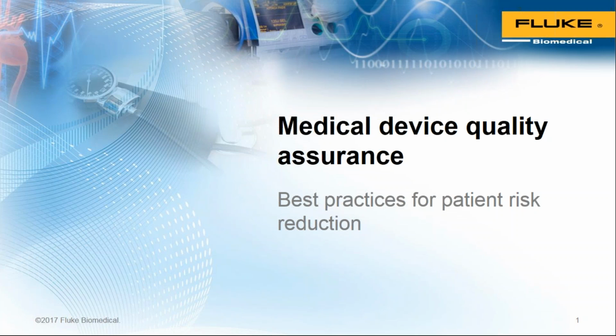Now there's another test that people sometimes confuse with this, and that is a HIPOT test. A HIPOT test does evaluate the insulation quality of the medical device, but it also is doing that at a very, very high voltage, and it is done for the purposes of safety agency listing. So this would be a UL or CSA test that would be done on a medical device as we do design validation testing. Sometimes it's used in a repair where we've really opened the device up very much, but not normally a test that we do in the biomed department in a hospital anywhere. It has to do with the safety agency labeling.